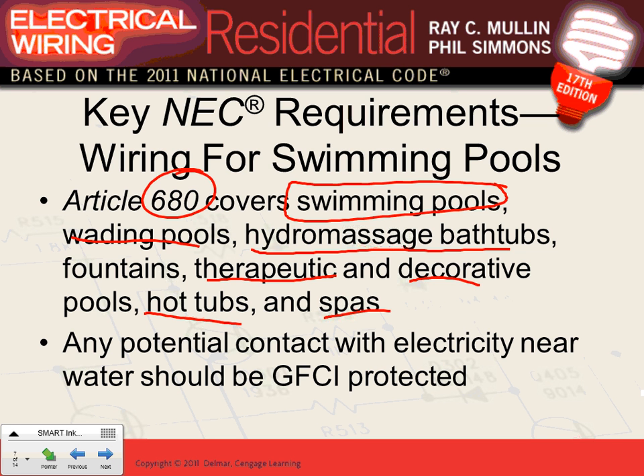Now, if anybody wants to guess, if you have a receptacle within the range of a swimming pool, what do you think a receptacle closer to a wet location has to be on? Anybody can guess, even without knowing the swimming pool rules? GFCI. That's the most important protection that can get you out of this situation. If your system is not grounded, guys, and you have GFCI protection, you will be protected, right? Because the current that goes in you and out of you will be seen inside the GFCI. Inside the GFCI, the difference in the current will make it trip.